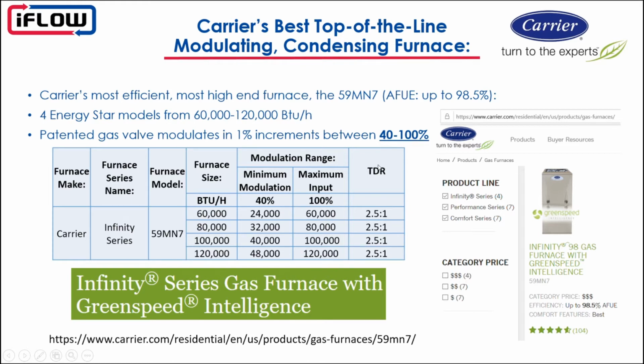So what that means is, if we take 40% of our 60,000 BTU input, that is 24,000 BTUs. So in this range from 24,000 to 60,000 BTUs, the furnace is going to modulate in 1% increments, which is excellent. So if you have a heat load of 45,000, 50,000 BTUs, for example, this could be a great furnace for you, and it will fully modulate in the range that you need.